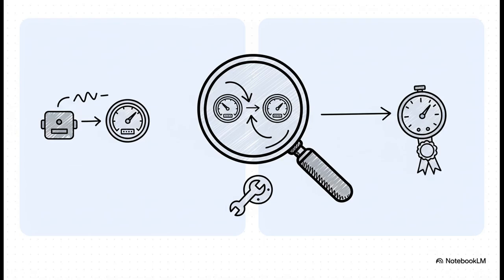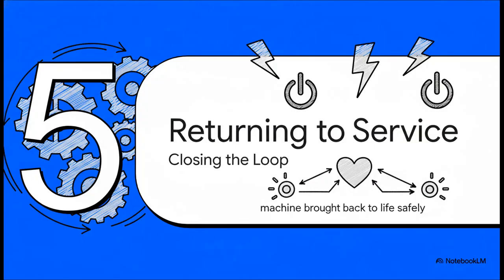So how do you make sure the machine's sensors are telling the truth? Well, you check them against a tool that you know is perfect. You compare the machine's sensor reading to a certified master gauge. It's kind of like setting your watch to the atomic clock. If the machine's sensor is off by more than that 1% we talked about, the technician fine-tunes it until it's perfectly in sync.